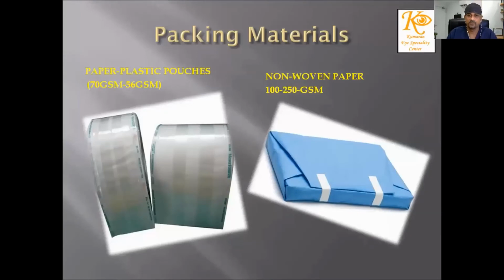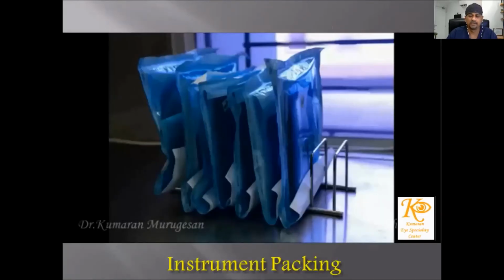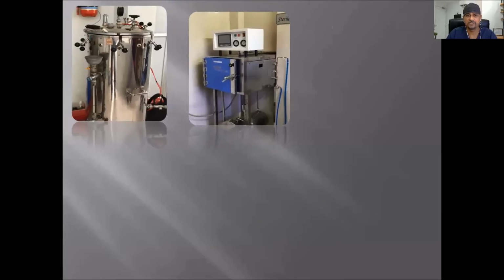Now the air dried instruments can be packed either in traditional linen, non-woven paper, or plastic paper pouches, and the thickness is indicated here. A small note while packing is that the instruments have to be packed individually, and they have to be packed allowing room between the trays so that it could allow steam to percolate inside. It's also good practice to place all the trays vertically for proper penetration of the steam into the instrument trays.